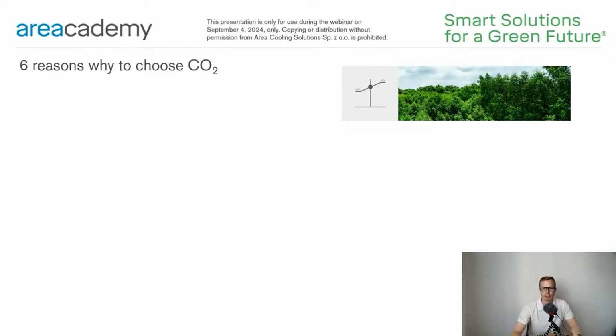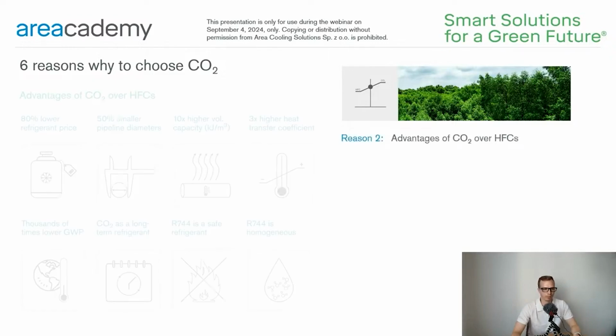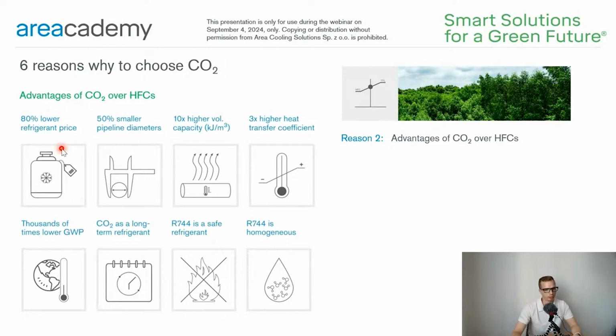Another reason why CO2 is an interesting refrigerant is the list of advantages of CO2 over HFCs. For example, the price of 1 kilogram of CO2 can be even 80% lower than 1 kilogram of popular HFC refrigerants. With the same installation capacity, the pipelines in case of CO2 will be about 2 times smaller, and this is because of the very high volumetric cooling capacity, which can be from 5 to even 10 times higher compared to HFCs. Thanks to the high heat transfer coefficient, heat exchangers such as gas coolers or internal plate heat exchangers can be compact and they can work at much lower temperature differences.